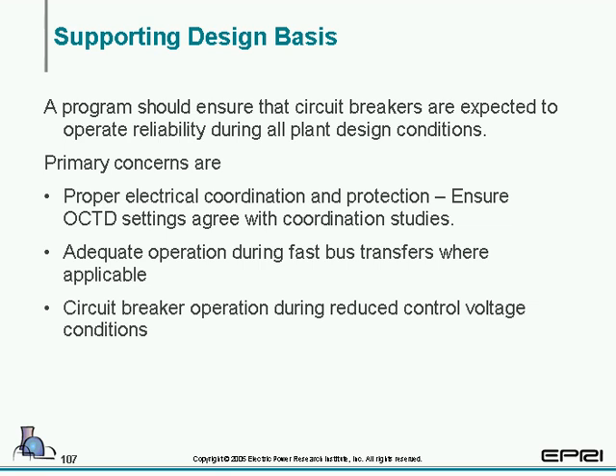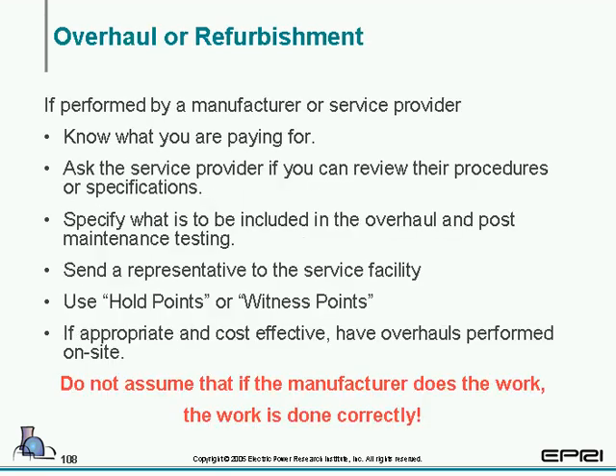Supporting design basis, again, this is primarily for the nukes, but obviously you need to ensure that throughout the life of the plant that electrical coordination and protection is maintained. Ensure your overcurrent trip device settings agree with your coordination studies. If you have fast bus transfers you need to worry about, that's something you need to consider. And also, if you have reduced control voltage conditions, will your circuit breaker operate? Those are some things you need to consider.